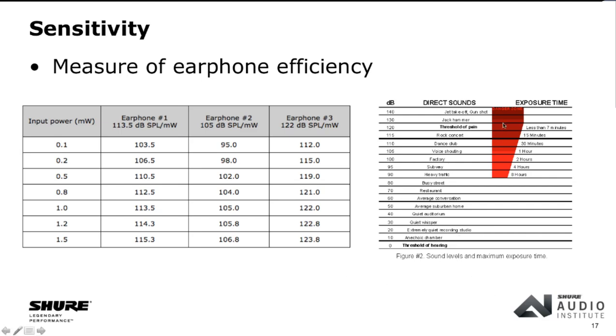Which is what you see in the area in the red here, kind of the danger zone when you start getting into how long you can listen to earphones at a certain level. So if we look at, say, you put a milliwatt into earphone number 3 and get 120 dB SPL out, that is above the threshold of pain, and OSHA doesn't recommend you be there for any longer than 7 minutes. And that's in a day. That's not in an hour. That's your daily exposure to that kind of sound pressure level, right? So again, louder is not necessarily better. Could be useful, but then you better be careful.